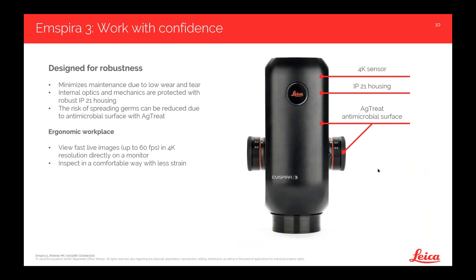IP with different number settings means that the housing is protected against particles that can come into the housing or against water. And depending on the number that you give, that varies in terms of what can happen. So the IP21 housing has been tested from us under vertical water flow and against entering of particles. Also, when Emspira 3 is sent out, all the connectors that are on the back are sealed with plugs, and you only open the plugs or the connections that you really need.